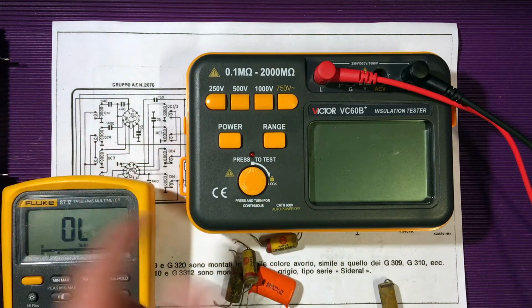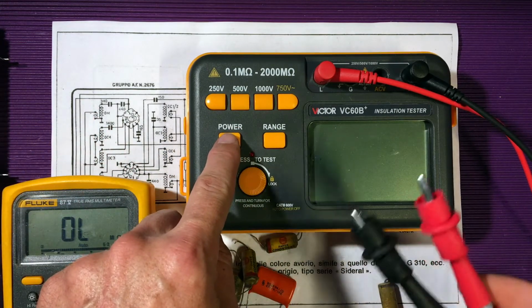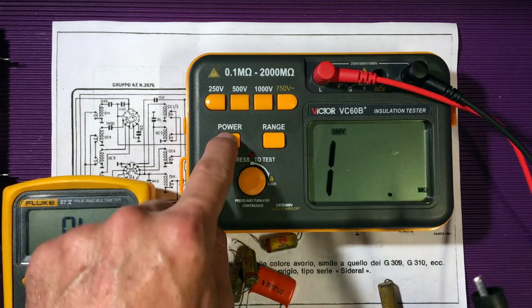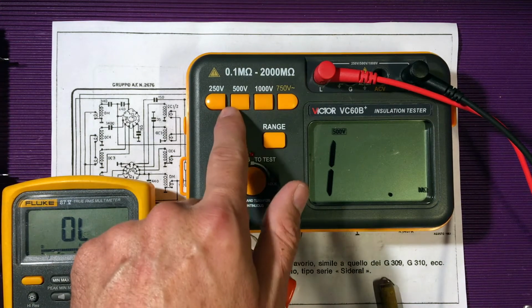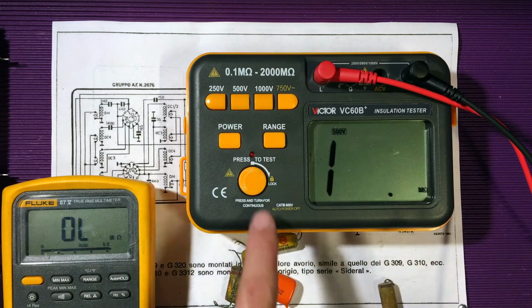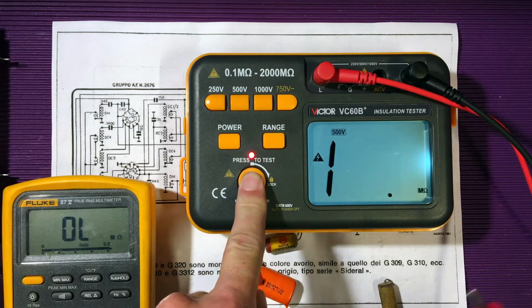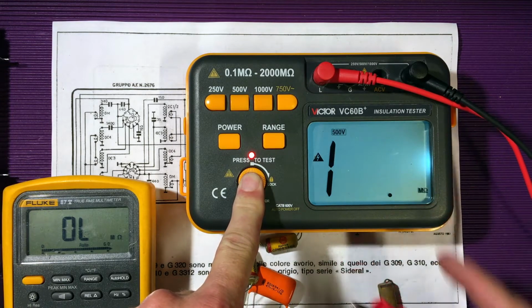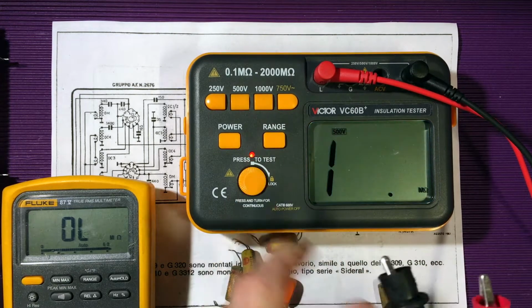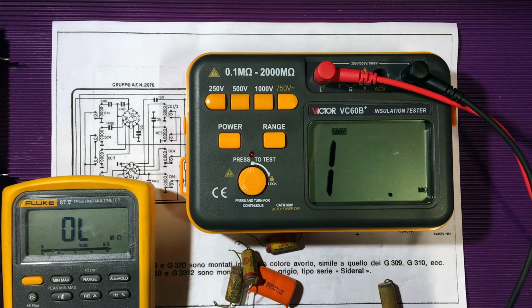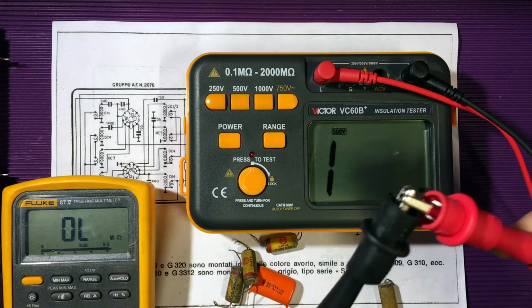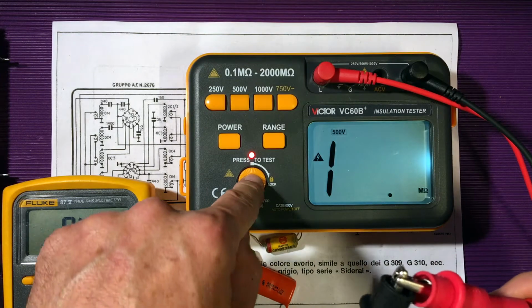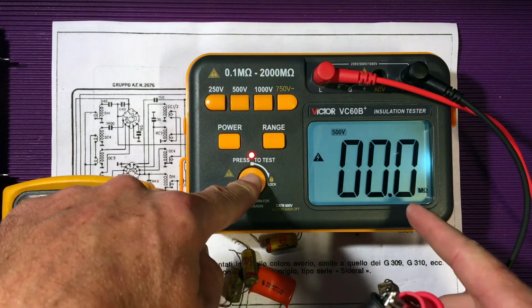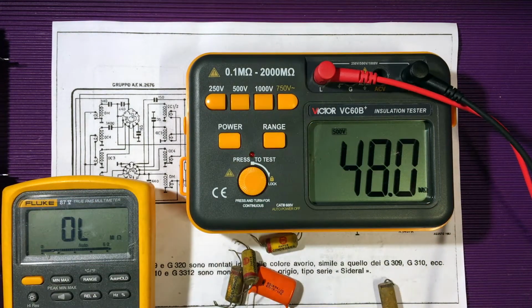It's not leaky. So for example, if I power it on, I have the test leads here, and we have it set to 500 volts for hand use. When you press test, well, it's open, so it measures overload in resistance. If I short the leads, when I measure, it shows 0. That's the way it works.